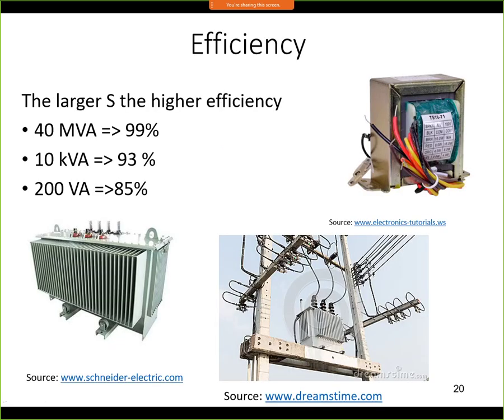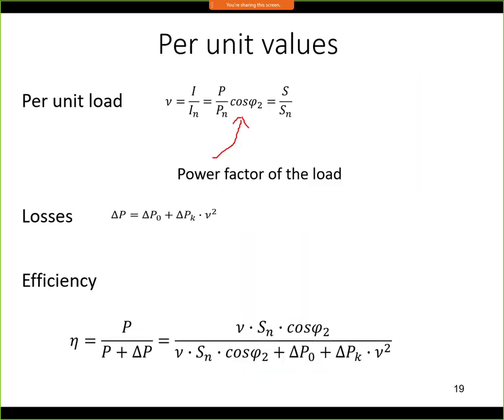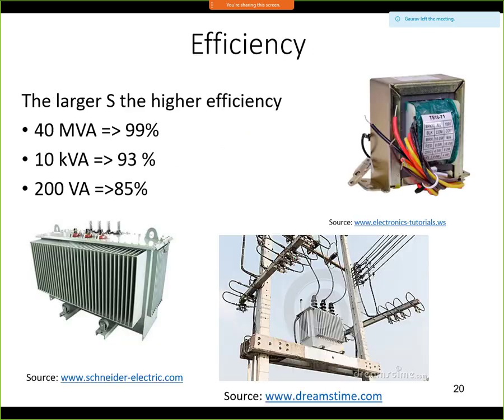The efficiency of a transformer is very high and increases with larger apparent power. Very large transformers of about 40 megavolt-amperes achieve approximately 99% efficiency. Small transformers of about 10 kilovolt-amperes have around 93% efficiency. Small transformers found in home appliances at 50 to 100 watts may have efficiency of only about 80 to 85%.